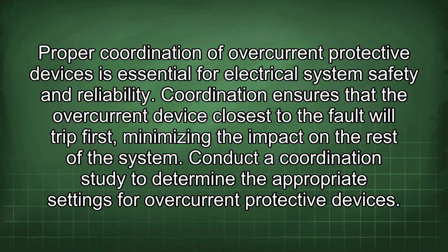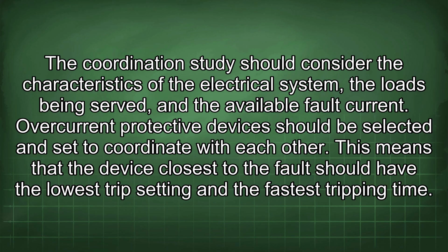Proper coordination of overcurrent protective devices is essential for electrical system safety and reliability. Coordination ensures that the overcurrent device closest to the fault will trip first, minimizing the impact on the rest of the system. Conduct a coordination study to determine the appropriate settings for overcurrent protective devices. The coordination study should consider the characteristics of the electrical system, the loads being served, and the available fault current.